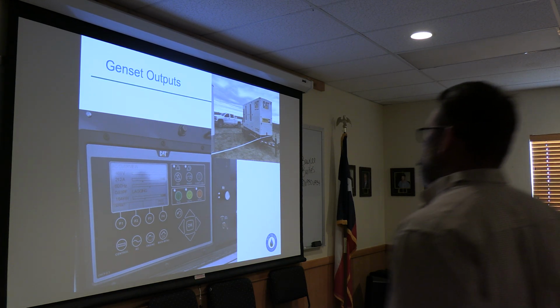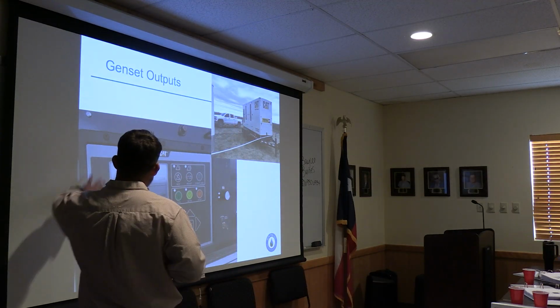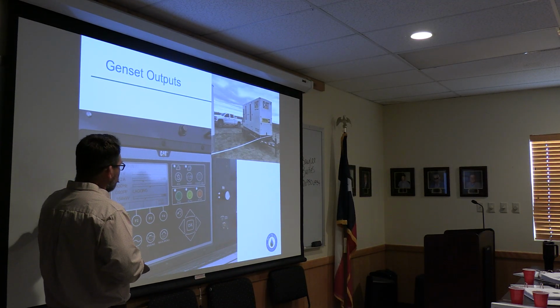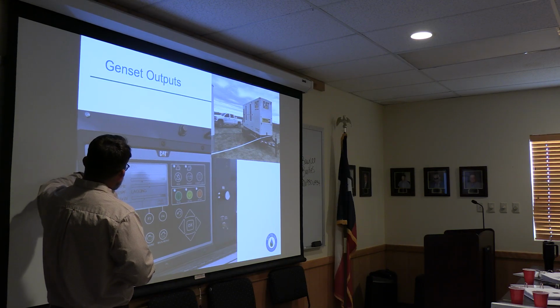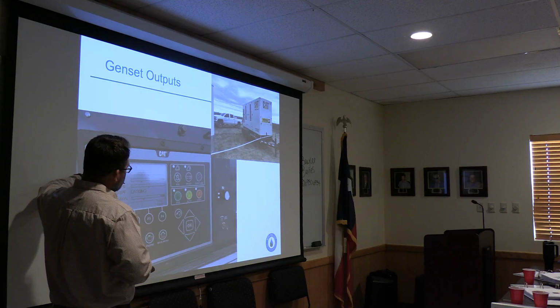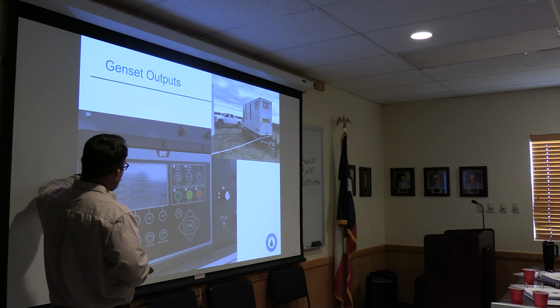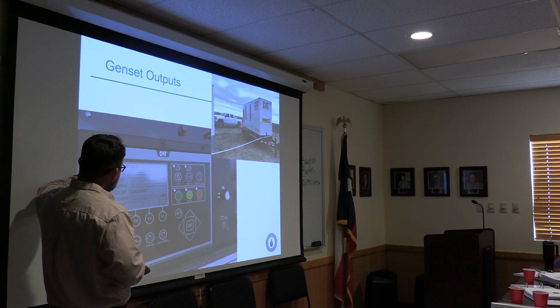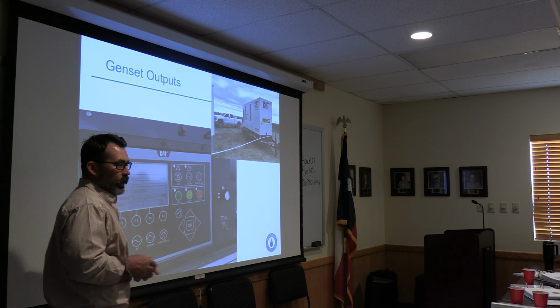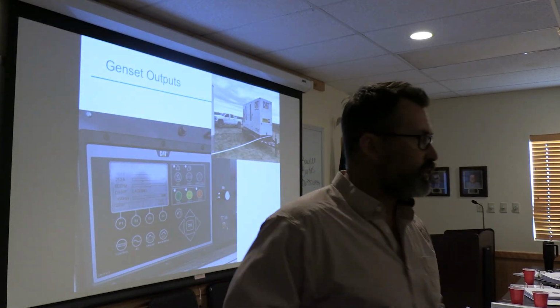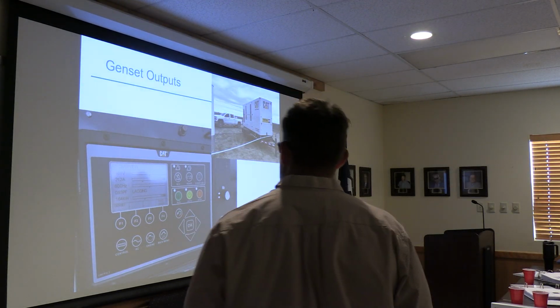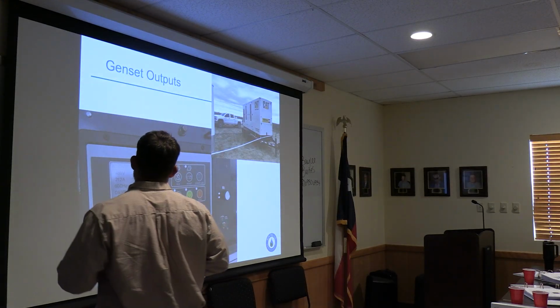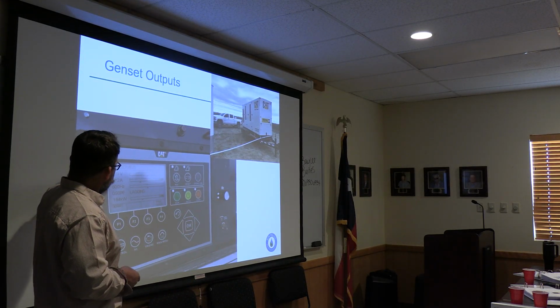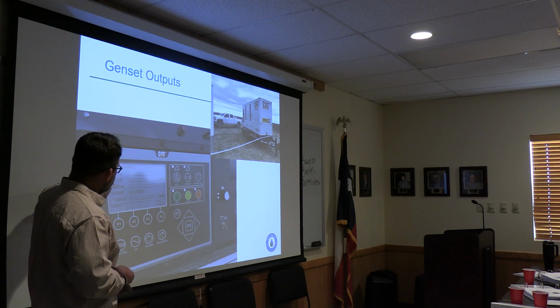So this would be an example of the gen set outputs. This is a digital screen, but typically this is going to be your control panel. Really pretty simple to understand. Telling you your voltage, 481 volts. Most gen sets are going to have a very robust regulator on it because you have to control for this voltage. And so the governor on a diesel gen set is going to be very, very strict. It's hard to defeat those governors. And you don't really want to defeat those governors because the system works together. So the output here is going to show 480 volts, 212 amps at 60 hertz.